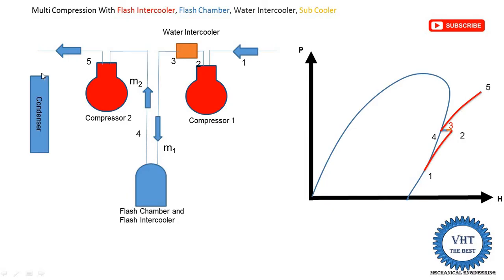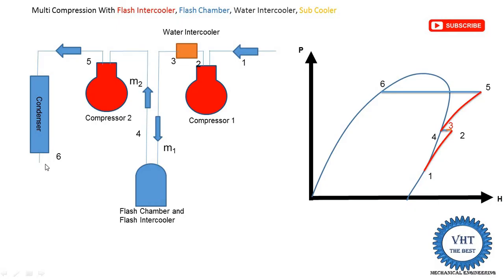The refrigerant is supplied into the condenser. The condenser is a heat exchanger where we reject heat to the atmosphere using a fan or water. The outlet point from the condenser is point 6. Since the condenser operates at constant pressure, it is isobaric heat rejection. At the inlet of the condenser it is vapor and at the outlet it is liquid, so we draw the horizontal line from point 5 towards the left to get point number 6.